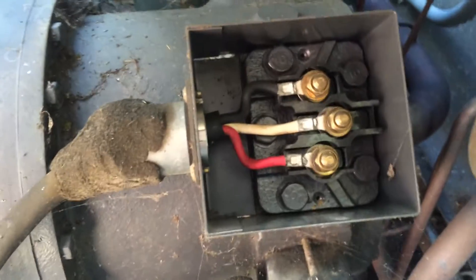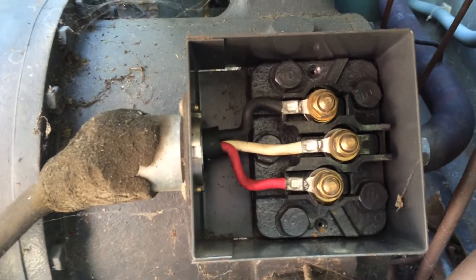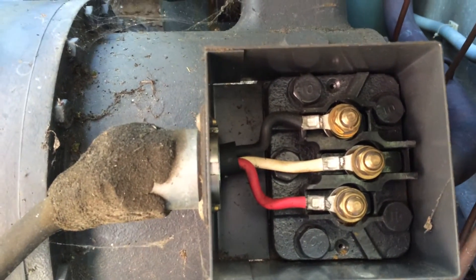It's quite a big breaker there - I think it's like a hundred amp, or a hundred and twenty-five amp or eighty amps or something. Substantial. So if you had a short on one of these, you'd expect to find the wire blown apart. There's not much wrong with that visually. If it was full of damp or anything, you might think it was a terminal - yeah, the plate just got damp.